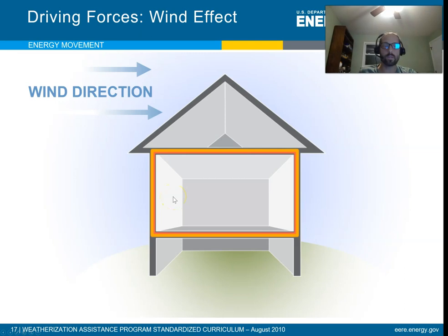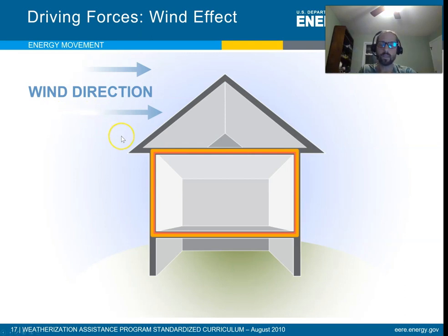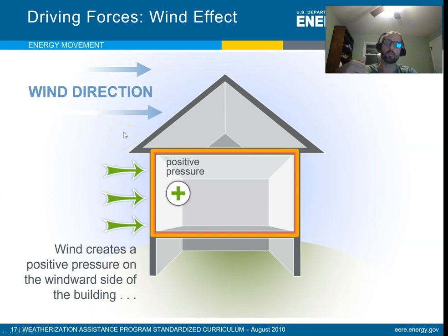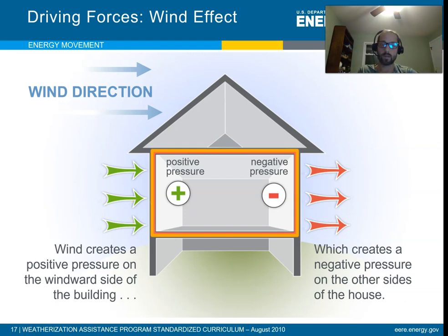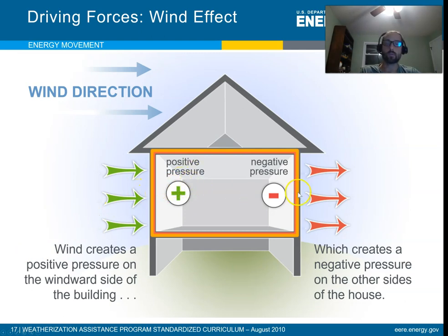First, the wind effect. When you have wind blowing primarily from one direction — in this case, left to right — it will cause a high pressure zone on the left side, or the windward side of the building. The leeward side will have a negative pressure zone. The relationship between pressure and airflow is that air flows from areas of higher pressure to areas of lower pressure, so this positive pressure causes air to move inside and outside the house.